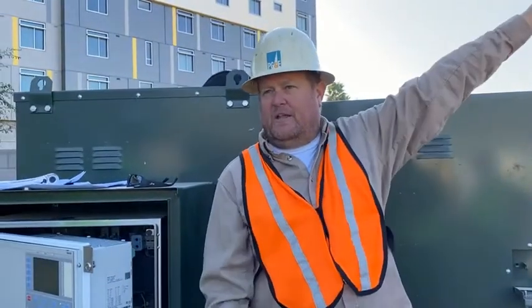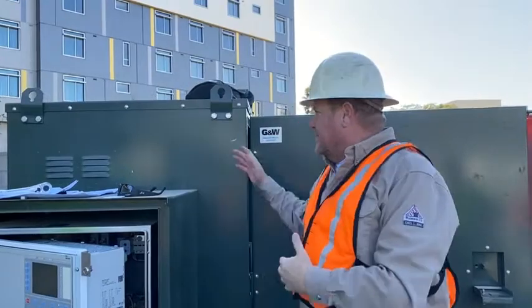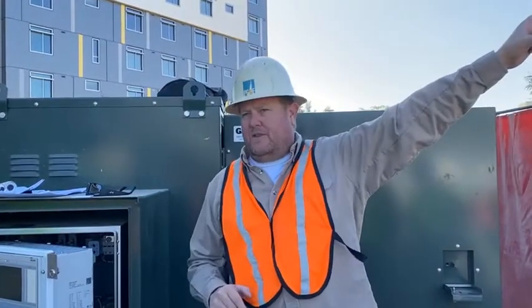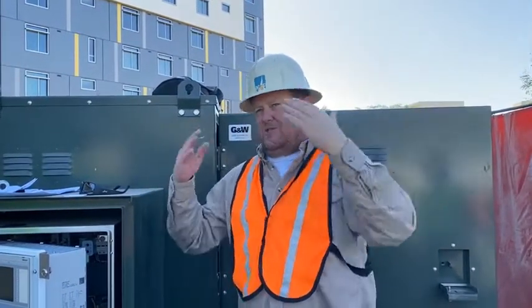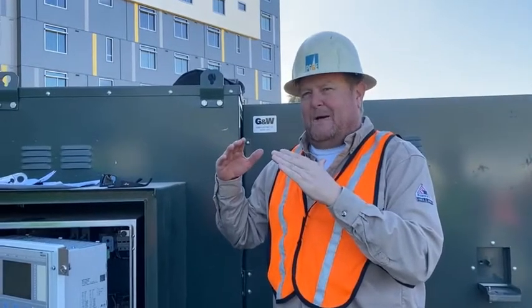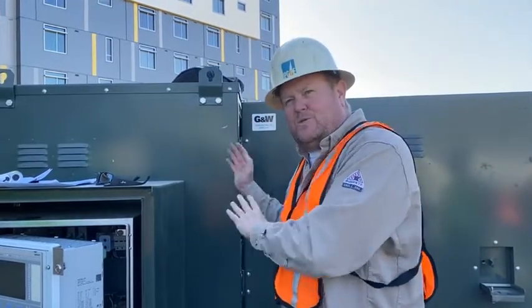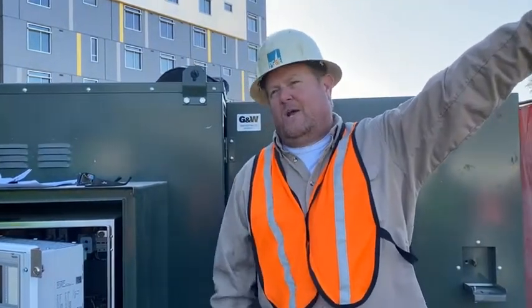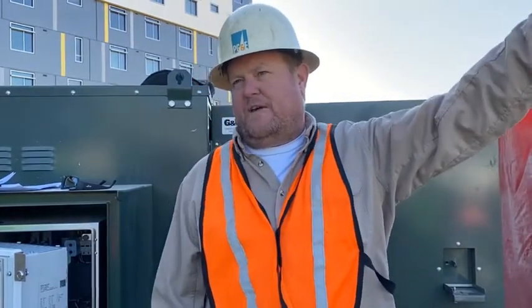You have a fault, it goes upstream. Well, the switches aren't going to stop the fault going upstream, because these are just switches. They're not designed to interrupt, so they're going to stay closed. These switches are going to stay closed and let that fault current go all the way back to your main switchgear. That feeder breaker is going to trip.